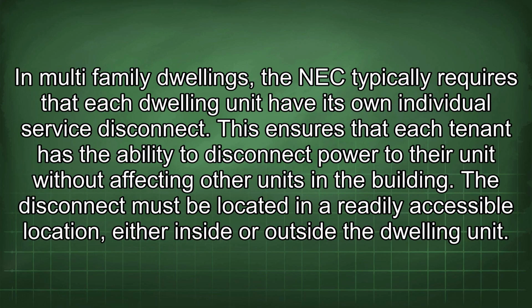In multi-family dwellings, the NEC typically requires that each dwelling unit have its own individual service disconnect. This ensures that each tenant has the ability to disconnect power to their unit without affecting other units in the building. The disconnect must be located in a readily accessible location, either inside or outside the dwelling unit.